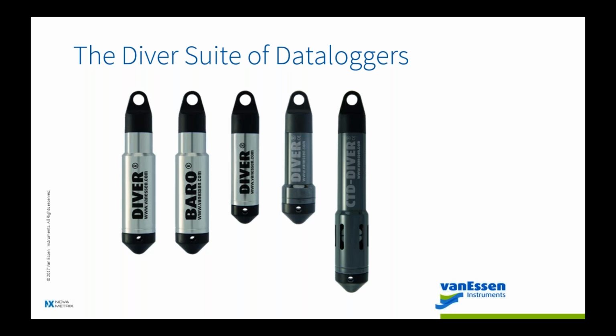The smallest diver that we have is also the smallest on the market. Nobody can beat this unit. It's a little bit larger than a chapstick. This unit fits in a 3/4 inch well with wiggle room. It is also short, so it bends around corners quite nicely. This unit is where we start to ramp up the electronics in terms of what they're capable of. We're moving away from just providing the fixed. We now add event-based, like the CTD, averaging, and preloaded pumping test, and obviously customizable pumping test.